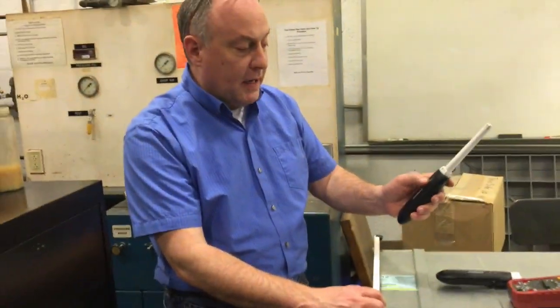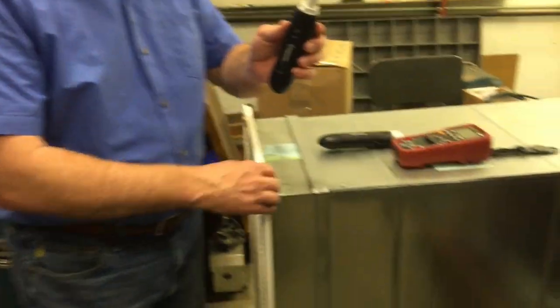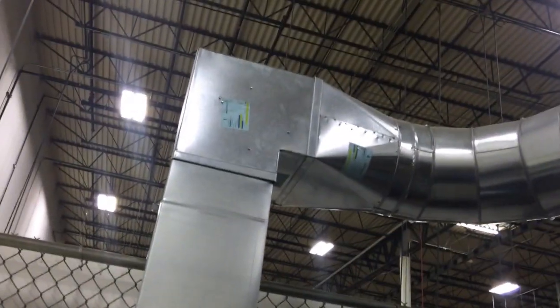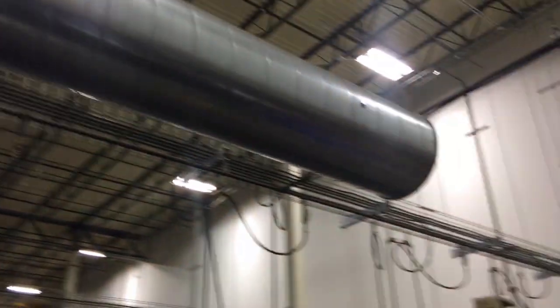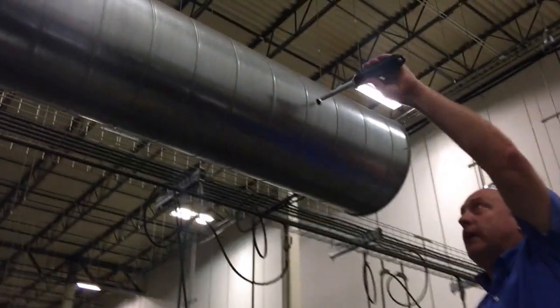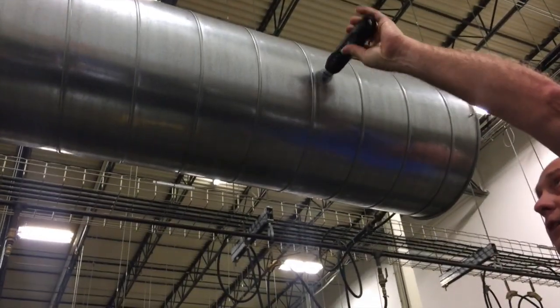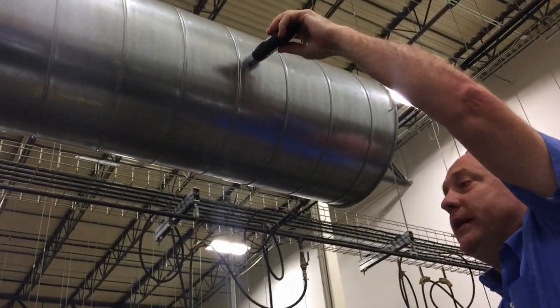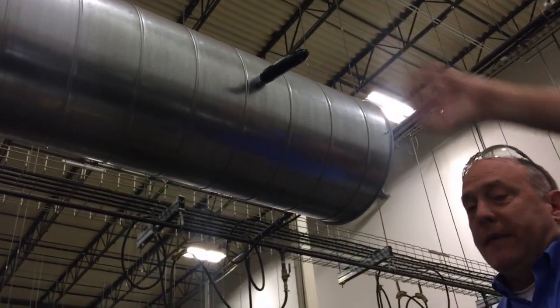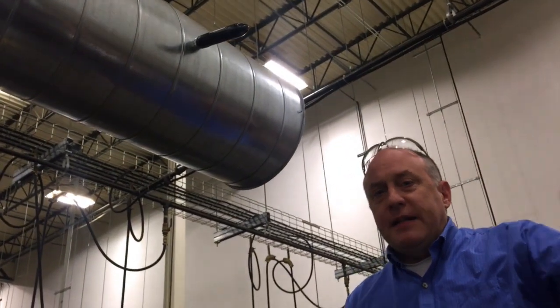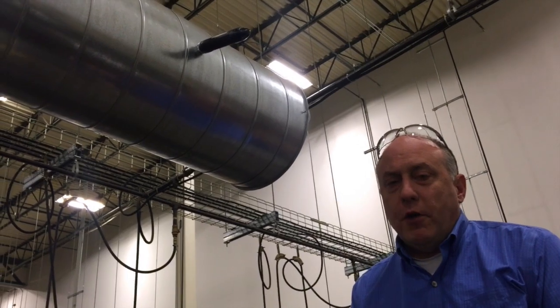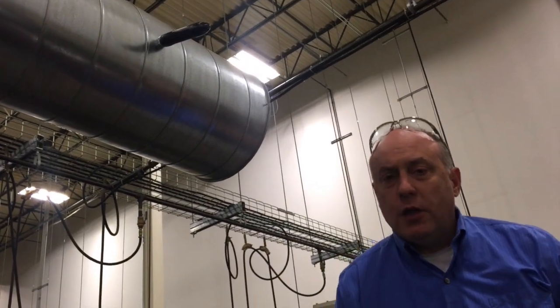Then I'm going to go ahead and turn on my supply probe, and what we want to do is we're going to put that up into our supply air register. And actually we're going to put it all the way at the end of the ductwork here. This is the very end of it. And what we're doing here is we're making sure that we're actually sampling from inlet to outlet. So we're going to see the total performance of the air conditioning system. So those two are hooked up and we're ready to go.